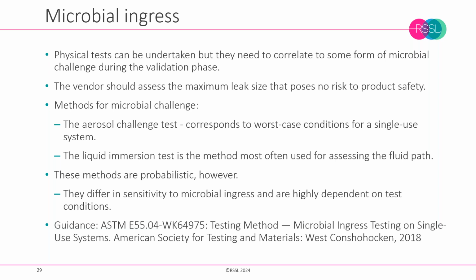So we can either have integrity testing, microbial testing, or a combination thereof. So with a lot of aseptic connector devices, often these are immersed in a microbial soup, and then something like a microbial culture medium is pushed down through the device and then evaluated with the requirement that the broth does not detect any contamination. There's always a weakness with these methods because they are probabilistic and they are highly dependent upon the test conditions. But this combination of integrity and microbial testing can be very useful, particularly when we're making, say, aseptically filled products, and we're very reliant upon these technologies to maintain sterility when they're connected together.